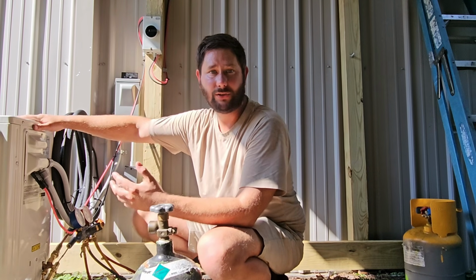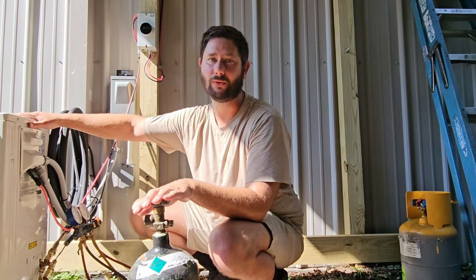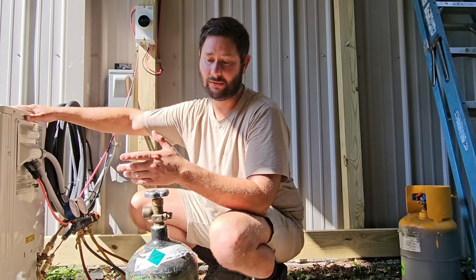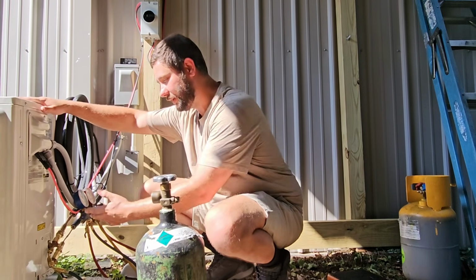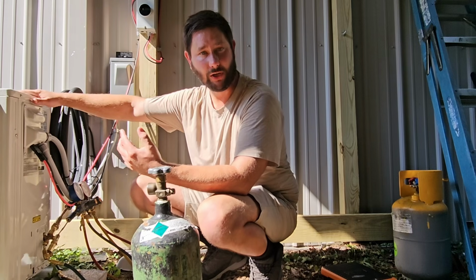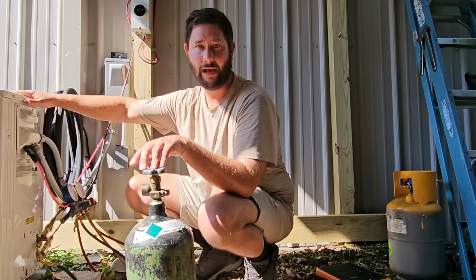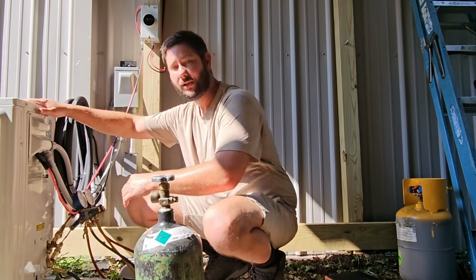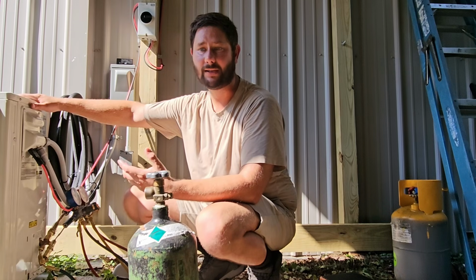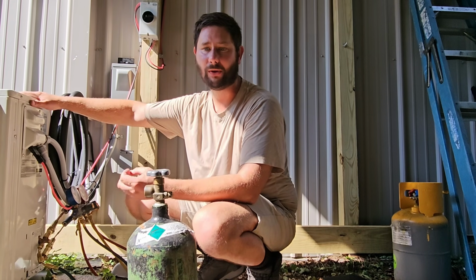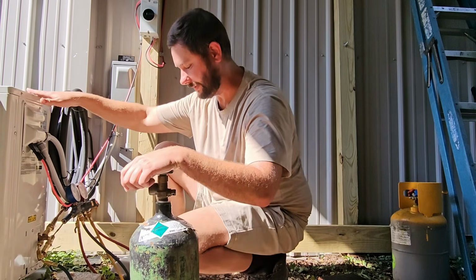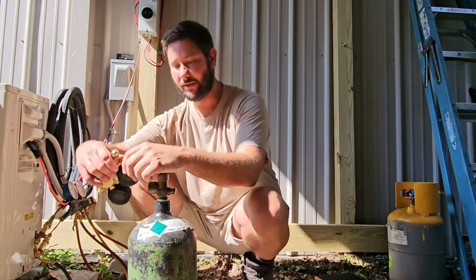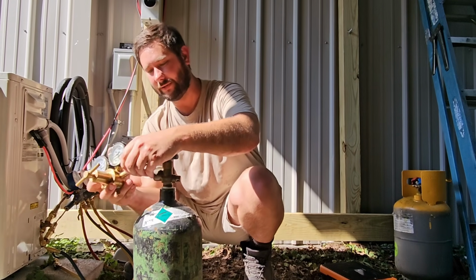You don't have to use nitrogen, but it's a good thing to do, especially if you want a really good vacuum pull. You can also use this for pressure tests. Say you have flare fittings on your outdoor unit and you want to do a soak test, you can actually use your nitrogen. If you have quick connectors, you do a leak test using a combustible gas leak detector or a refrigerant leak detector. So to use a nitrogen tank, we have to have a regulator, right?